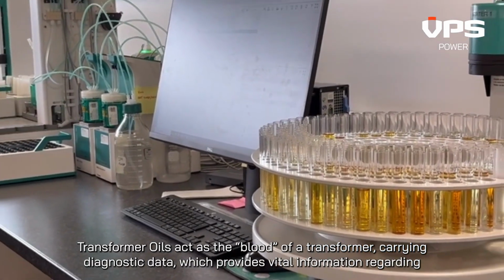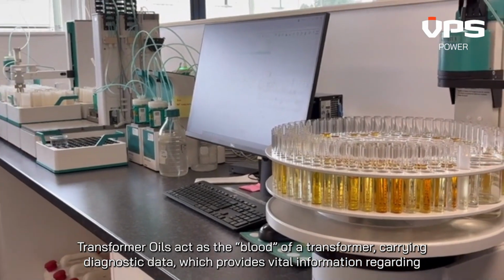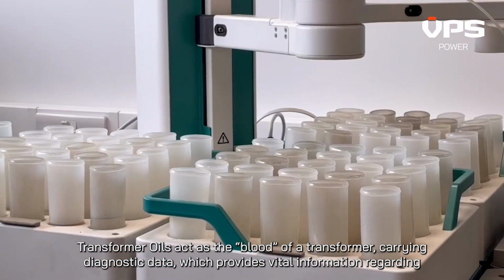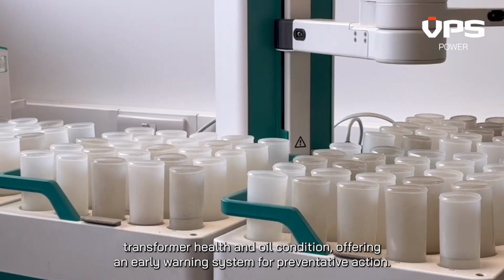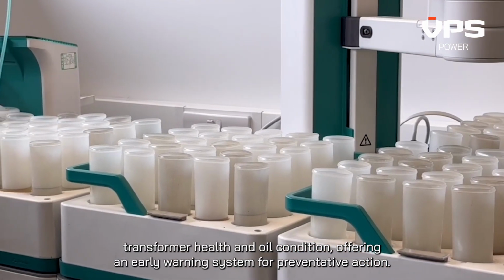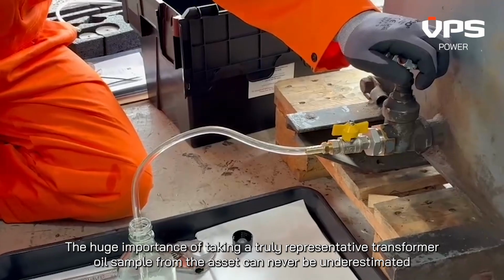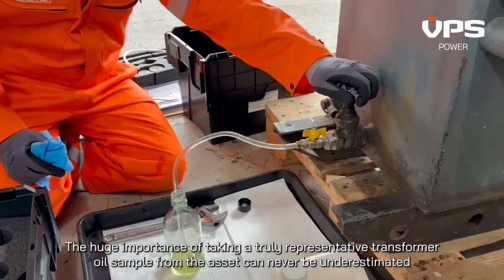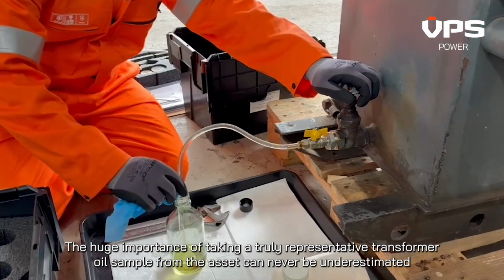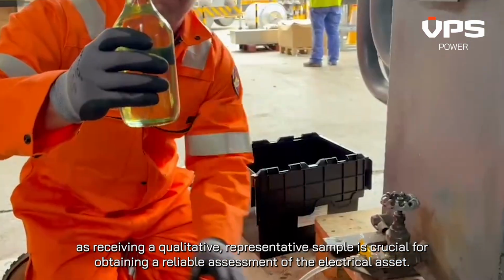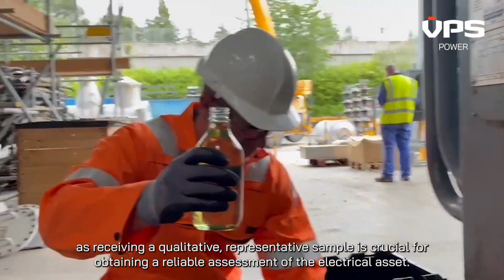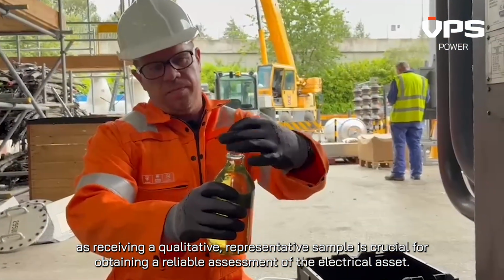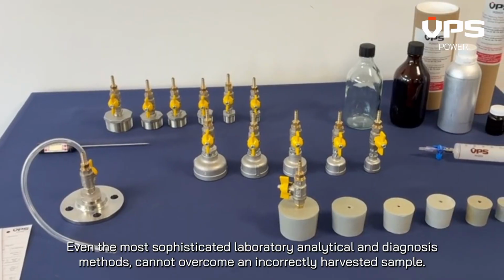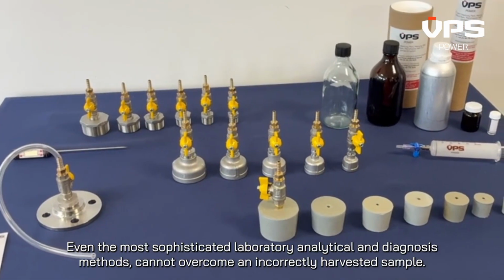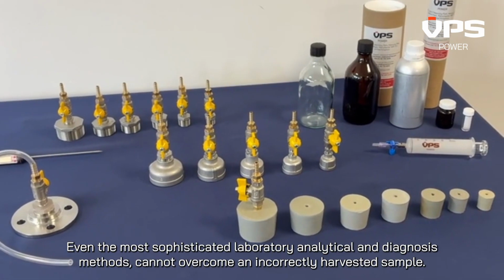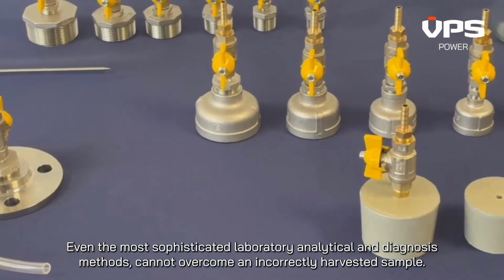Transformer oils act as the blood of a transformer, carrying diagnostic data which provides vital information regarding transformer health and oil condition, offering an early warning system for preventative action. The huge importance of taking a truly representative transformer oil sample from the asset can never be underestimated, as receiving a qualitative representative sample is crucial for obtaining a reliable assessment of the electrical asset. Even the most sophisticated laboratory analytical and diagnosis methods cannot overcome an incorrectly harvested sample.